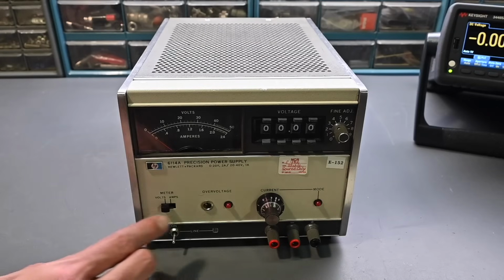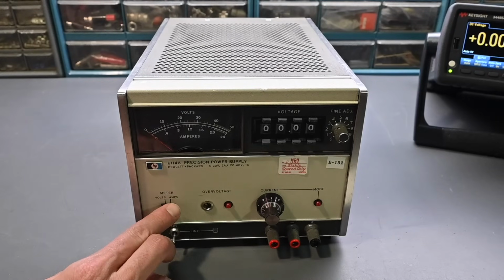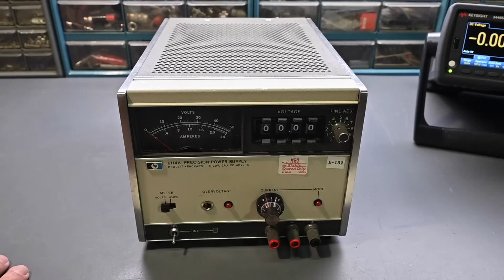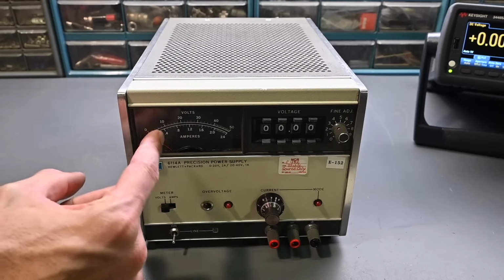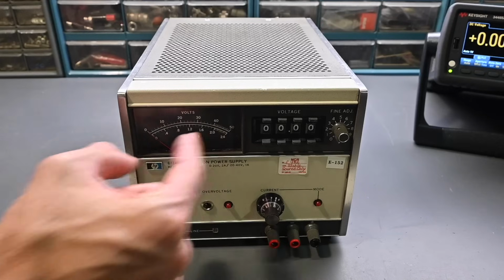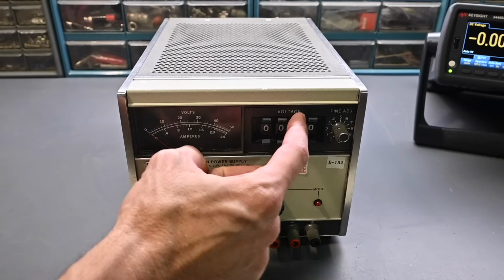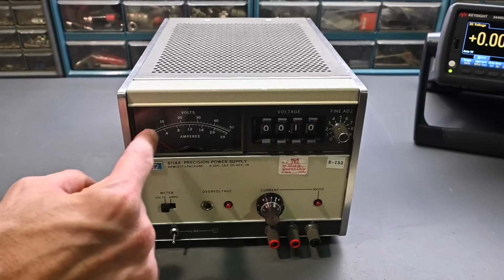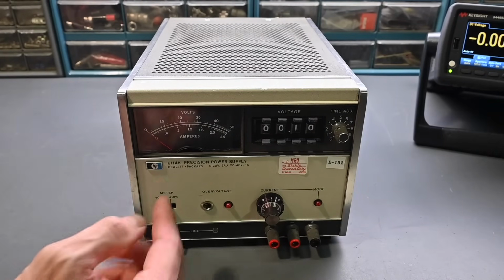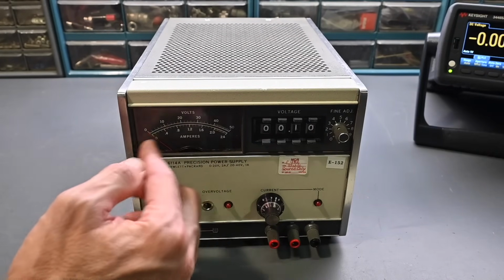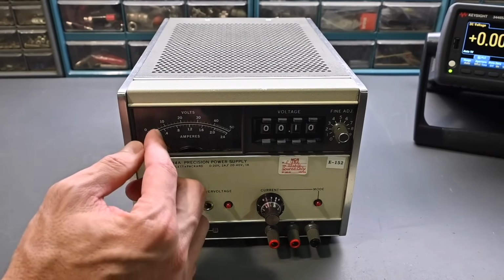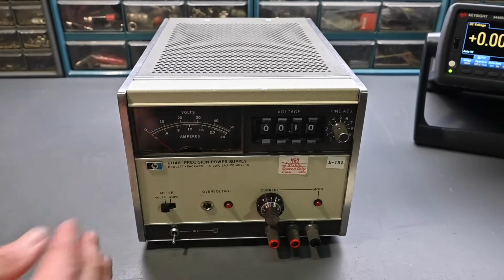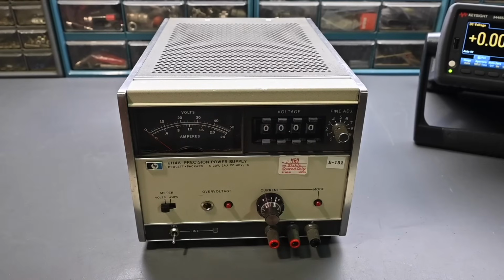Now over here you have a selector for the meter for volts or amps, so you can see the two scales on the meter. Obviously with this meter and the way the tick marks and values are on that scale for voltage, if you had that set to 100 millivolts, you're basically not going to see any movement on the meter. This is just for confirmation that you are getting some voltage, but it's not going to show the very fine values down here. You would just trust that the meter is accurate or use an external meter to monitor.